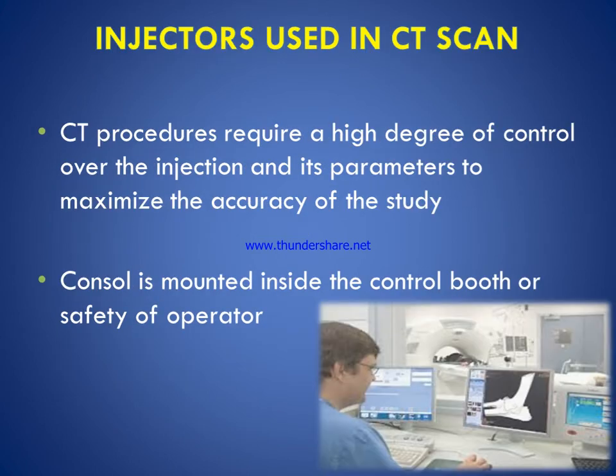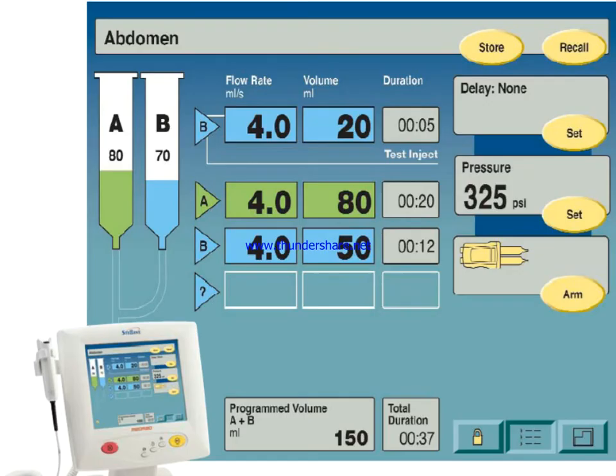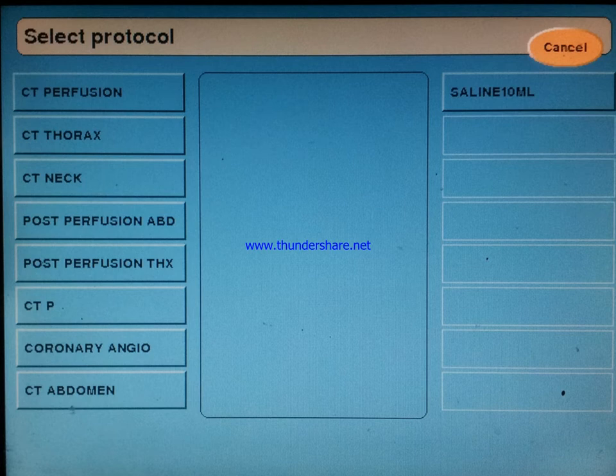For CT procedures, a high degree of control over the injection and its parameters is required to maximize the accuracy of the study. The console is mounted inside the control booth for the safety of the operator. The flow rate is programmed from 0.1 to 9.9 ml per second, with dual programming offering a choice of flow rate per volume or flow rate per duration. For example, for abdomen protocol, a flow rate of 4.0 ml per second with 20 ml contrast volume and 5 second duration may be used.